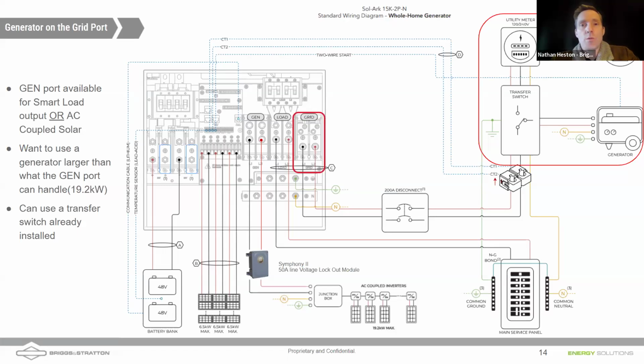In doing so, they can send power back to the generator and potentially damage the alternator. So we don't want AC coupled solar ever backfeeding the generator. There's no value for that, right? We're not gaining gaseous fuel back by running that generator backwards.